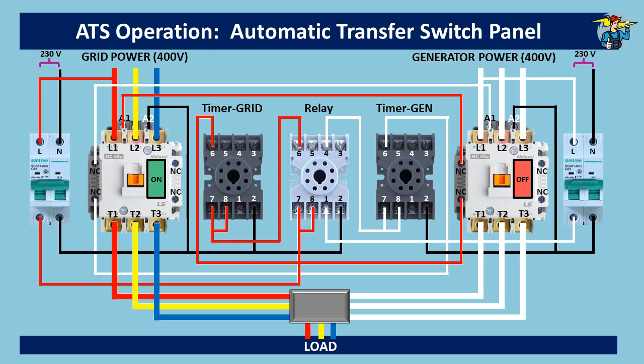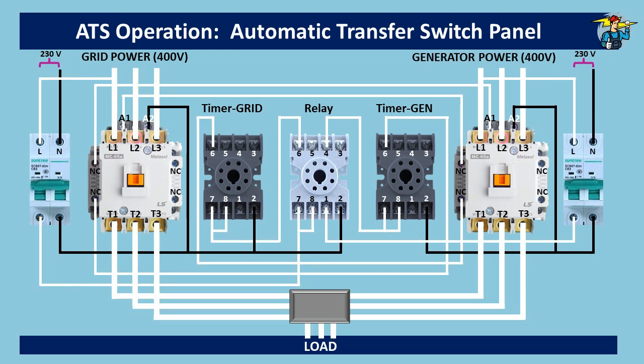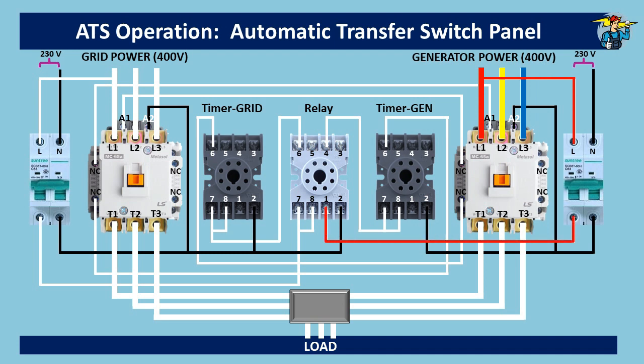Now let's see what happens when grid power is interrupted. Generator auto-starting is not included here and will be discussed in a separate video, so we need to start the generator manually. Three-phase power will then be available at L1, L2, and L3 of the generator contactor. The control circuit breaker on the generator side allows power to common port 1 of the relay. The line to port 7 is still energized and the relay is not powered yet.